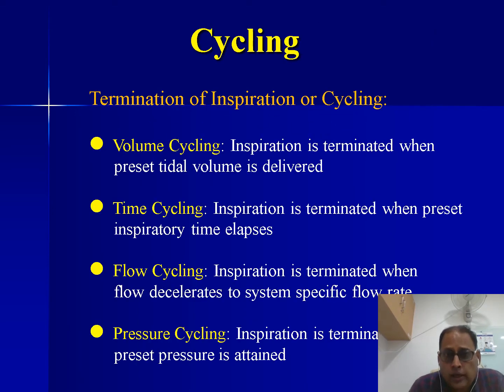Now coming to cycling, as I said, cycling is the termination of inspiration. It could be a volume cycled breath where the inspiration stops when a particular preset tidal volume has been delivered. It could be a time cycled breath where inspiration is terminated when the preset inspiratory time passes. It could be a flow cycled breath where inspiration is terminated when the flow comes down to a particular set level from a higher level. Or it could be a pressure cycled breath where inspiration is terminated when the preset pressure is reached.